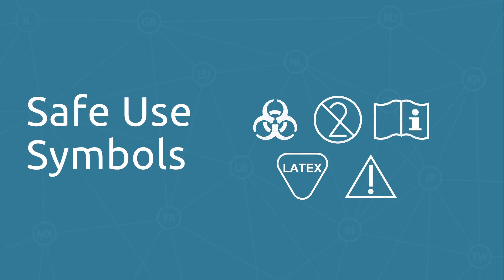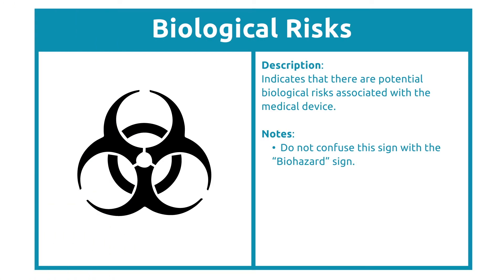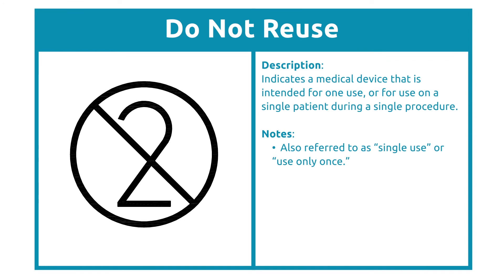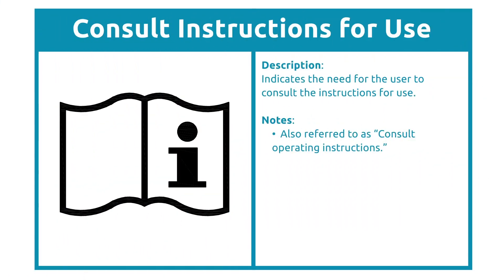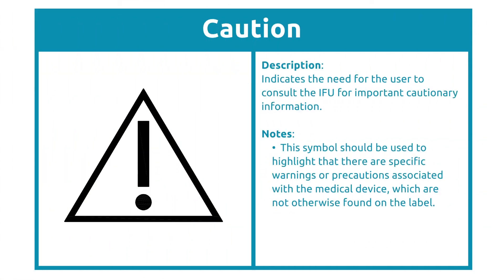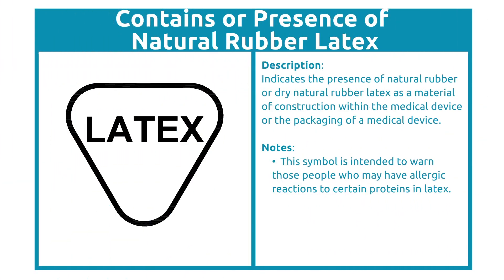Some medical devices present risk to the user. These Safe Use symbols act as a warning to reduce some of that risk. The Biohazard symbol denotes the presence of a biological agent — you might see this on a sharps container or other devices that have contact with biological materials. Devices categorized as single-use are labeled with that symbol. The Consult Instructions for Use symbol tells the user to read the included documentation when safety information requires more space than the label provides. The Caution symbol informs users to take extra precautions and that more detailed information is available in the instructions for use. Many people have an allergic reaction to latex, and this symbol serves as a warning to them.